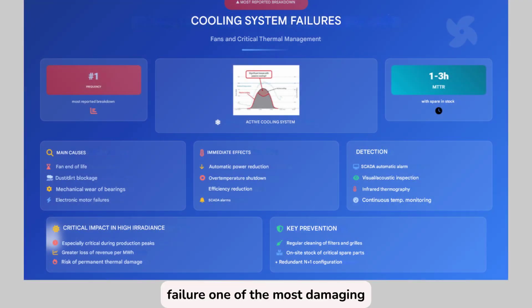From a financial perspective, the problem is even more significant. While repairs may not entail a significant cost, the loss of production during key hours, such as midday in the summer, represents a significant drop in revenue per MWh. Furthermore, failure to act quickly can lead to secondary damage that requires costly repairs. All of this makes this failure one of the most damaging silent leaks for a plant's profitability. That's why it's key to implement preventive measures.